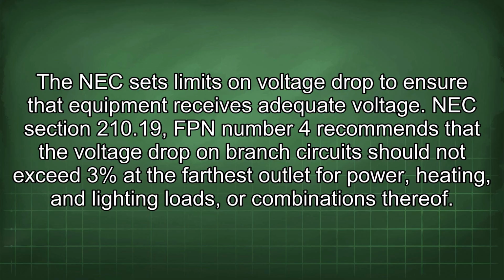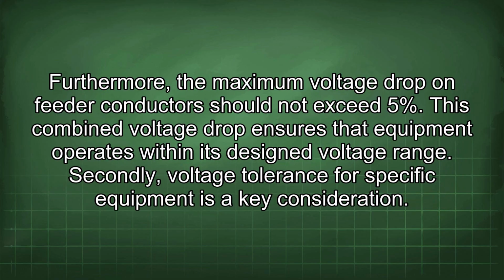NEC Section 210.19, FPN number 4 recommends that the voltage drop on branch circuits should not exceed 3% at the farthest outlet for power, heating, and lighting loads, or combinations thereof. Furthermore, the maximum voltage drop on feeder conductors should not exceed 5%. This combined voltage drop ensures that equipment operates within its designed voltage range.